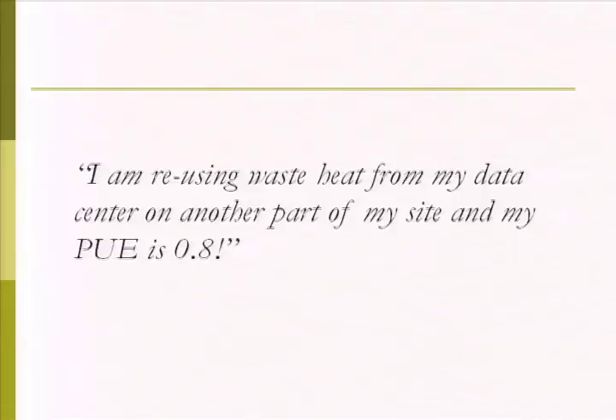Beyond 1.5, you can get there with things like free cooling. A lot of centers are very close to 1.0, including the Leibniz Supercomputing Center and, in the US, the National Renewable Energy Lab. So, say I'm reusing waste heat from my data center in another part of my site, and my PUE is 0.8 — not allowed, right? PUE can never be less than 1.